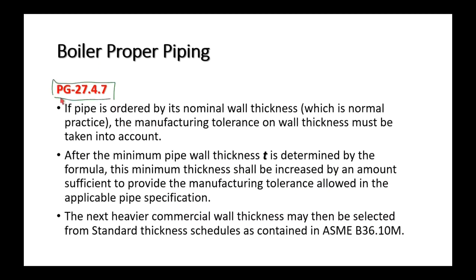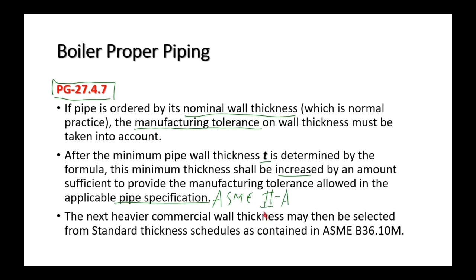PG-27.4.7 discusses nominal wall thickness: after calculating t using the formula, the minimum thickness must be increased by an amount sufficient to provide for the manufacturing tolerance allowed in the applicable pipe specification. You'd go to ASME II-A to find that tolerance — typically plus or minus 12.5% for most pipe. Then, after determining the increased thickness, select the next heavier commercial wall thickness.